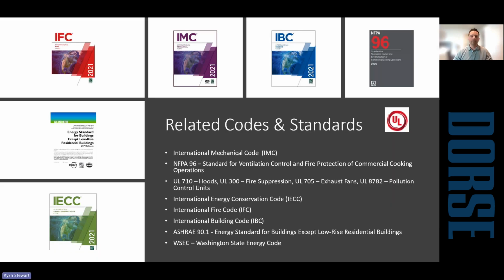So to start off, I just want to briefly touch on the codes. Since there's so many products that are incorporated into the system, they touch a bit on everything. The big one's going to be the International Mechanical Code. Then you have NFPA 96 for standards associated with kitchen ventilation and fire protection. Various UL listings depending on the products. UL 710's big for hoods, UL 300 for suppression, 705 for exhaust fans, and then there's some new listings for pollution control equipment. You have energy codes, fire codes, building codes. The ASHRAE 90.1 is a big one, and then Washington State Energy Code.